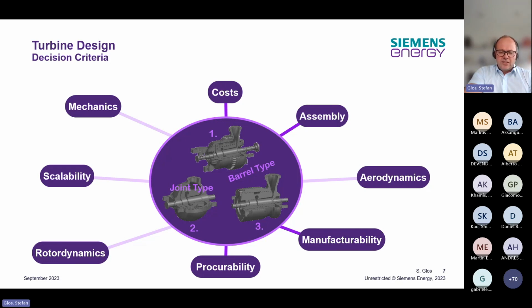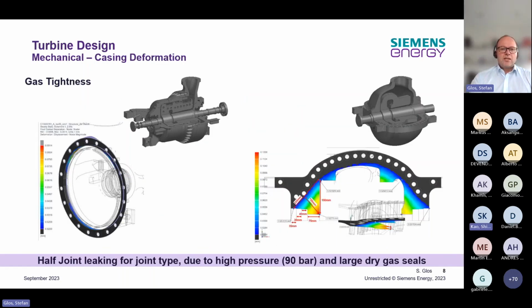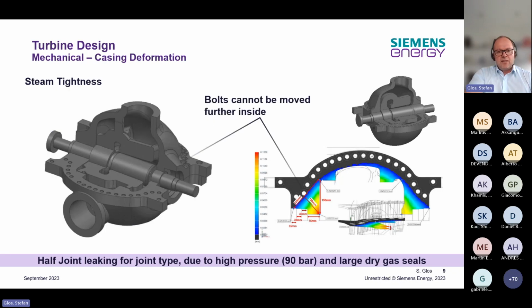And I will go a little bit into detail on one aspect which we checked and which was a significant drawback for this joint type turbine on the right hand side, which was the gas tightness. Due to the high pressure and the fact that we had to implement the dry gas seal in the outer casing, the gas tightness was really hard to realize, whereas in the left concept, the barrel type machine, this was really no issue. Here you see it once again with another drawing, and this was really one of the largest drawbacks of this joint type turbine.